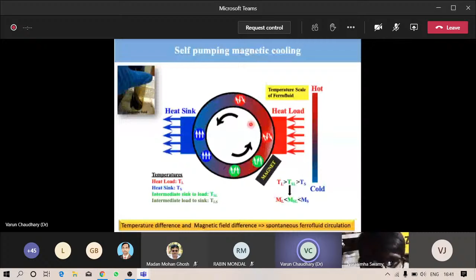Here, let's say this is the cold ferrofluid, and this is the heat load and heat sink. Because of the heat load, the ferrofluid becomes hot. When we apply the magnetic field, the cold ferrofluid is attracted by the magnet, while the hot ferrofluid doesn't interact with the magnet because after a certain temperature it reaches its Curie temperature. So because of this thermomagnetic effect, it circulates spontaneously, driven by the temperature difference and magnetic field difference.